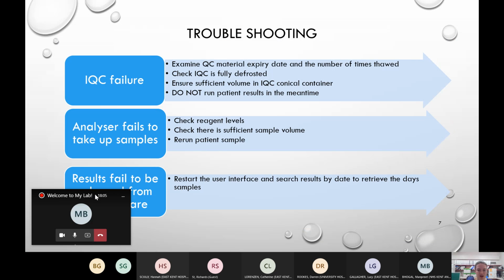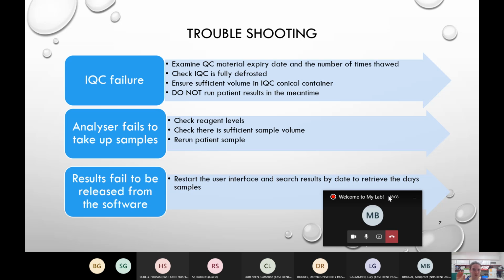There we go. So just on this side here, I've put a couple of examples of troubleshooting that I might have had to do during my time at QEQM and setting up the analyzer, that helped teach me to get into the hang of dealing with analyzer problems, because that's quite a common thing in the lab. So for example, if an IQC failure popped up, the process I'd go through in my head was to make sure that the material was in date and that it had completely defrosted, because if it was still frozen, the analyzer couldn't aspirate it and that could cause an error.